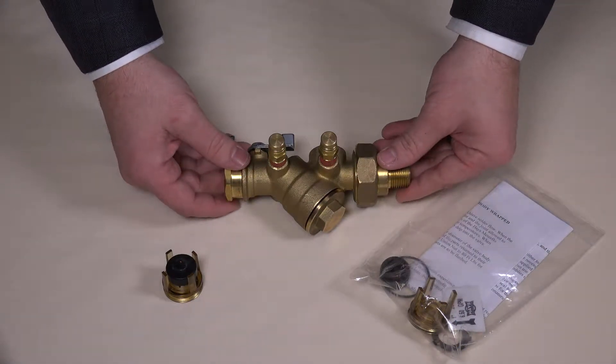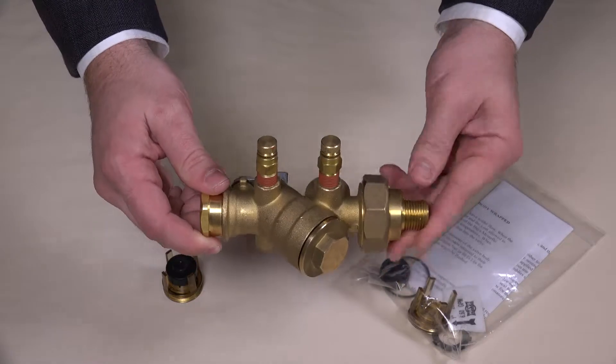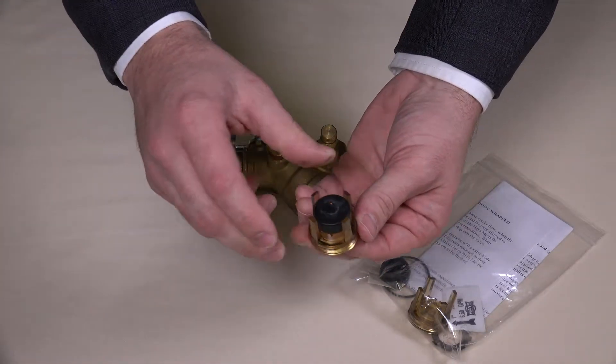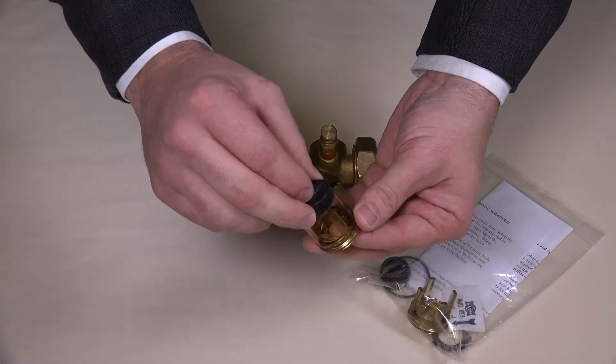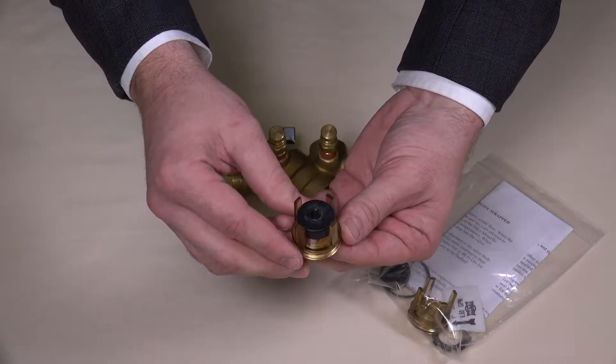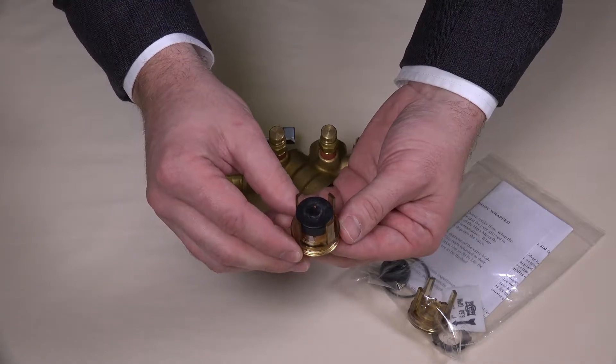The sample we will use today is the Hays Model 2514 automatic balancing valve. The balancing components are what we consider our Mesurflo design. These consist of two components: the diaphragm and the orifice plate. These pieces work in conjunction to limit the total flow to a desired amount, often the maximum GPM allowed through a coil.